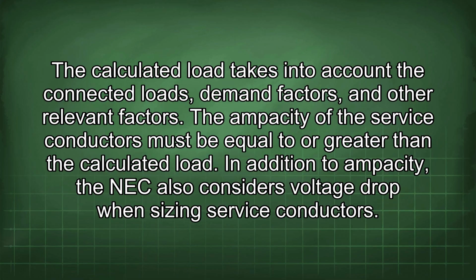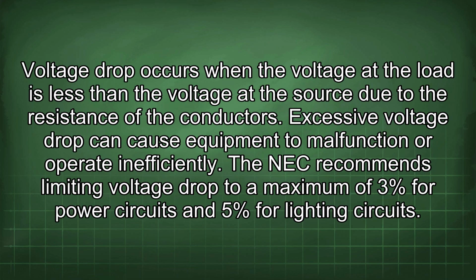In addition to ampacity, the NEC also considers voltage drop when sizing service conductors. Voltage drop occurs when the voltage at the load is less than the voltage at the source due to the resistance of the conductors. Excessive voltage drop can cause equipment to malfunction or operate inefficiently. The NEC recommends limiting voltage drop to a maximum of 3% for power circuits and 5% for lighting circuits.